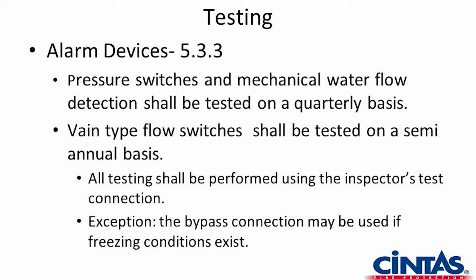The inspector's test connection generally will be located on the opposite end of the system from the riser. What we're looking for is that when we open that inspector's test valve, we start timing. Within 90 seconds of opening that valve, the alarm has to be notified. So we have to have an alarm within 90 seconds of opening the inspector's test valve.